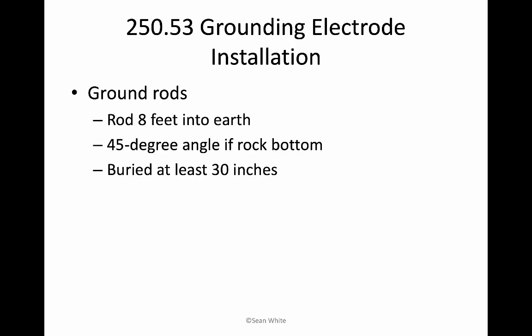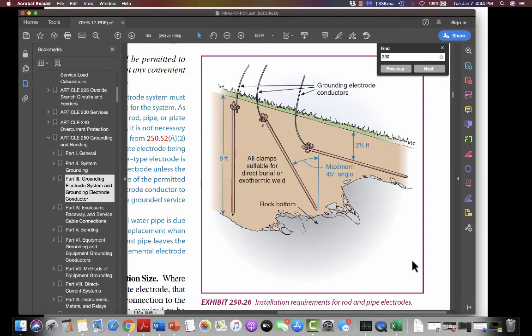So, installing the ground rod. The rod has got to be 8 feet into the earth, at a 45-degree angle if you hit rock bottom, as we're going to see in a picture in a second, and buried at least 30 inches. And here's a good picture of what we're talking about. There it is, 8 feet down. If you can do that, that's the best way to do that.